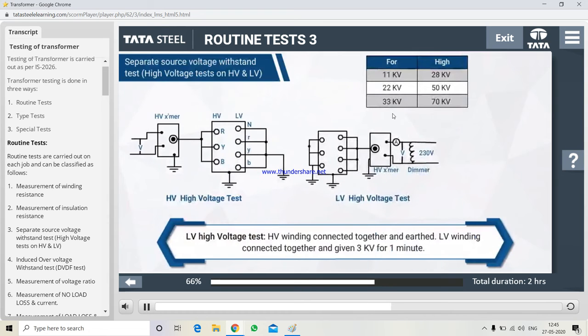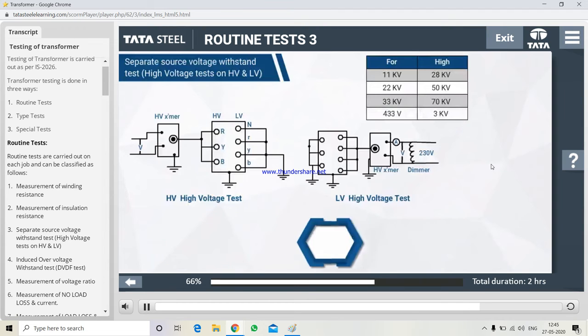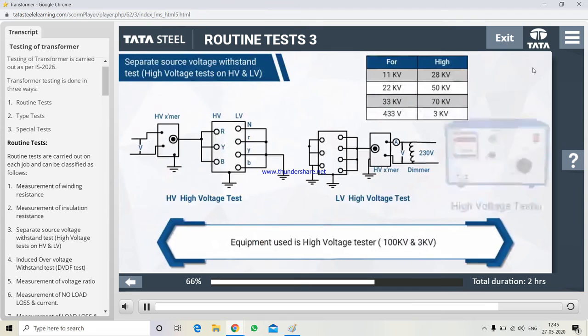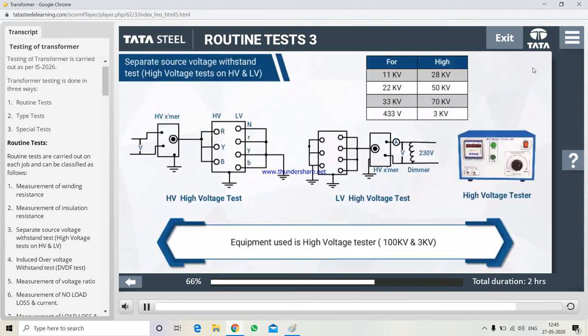LV high voltage test: HV winding connected together and earth. LV winding connected together and given 3 kV for 1 minute. Equipment used is high voltage tester, 100 kV and 3 kV.